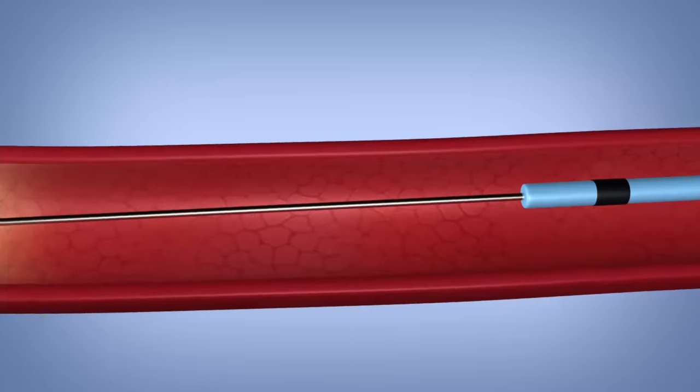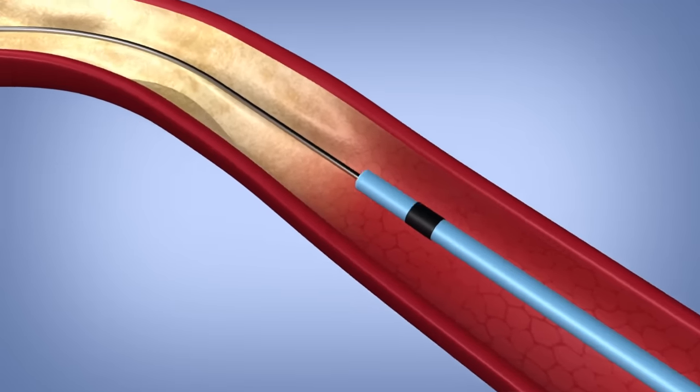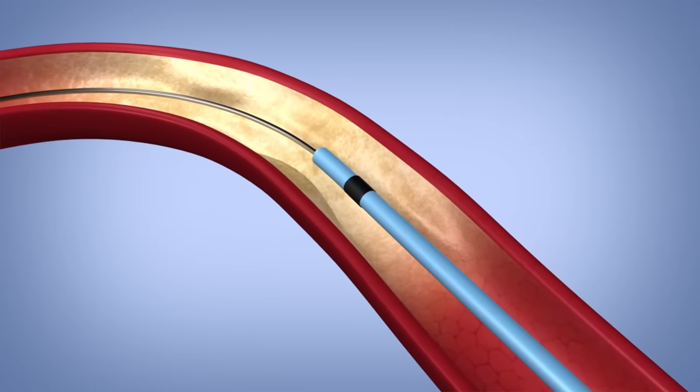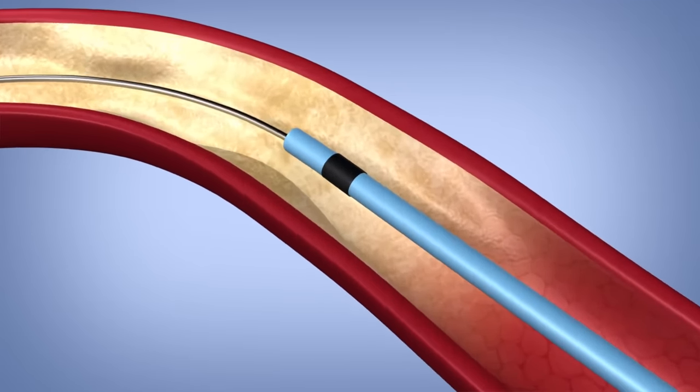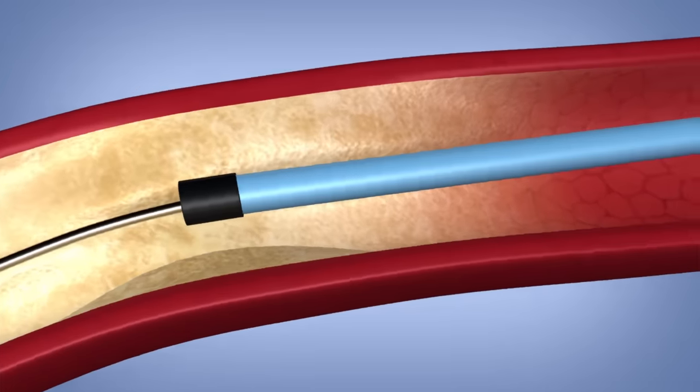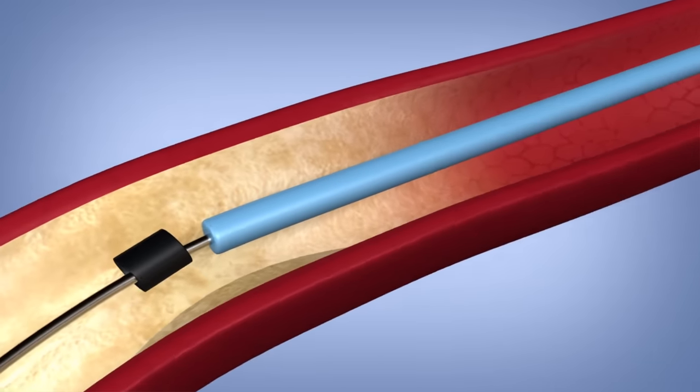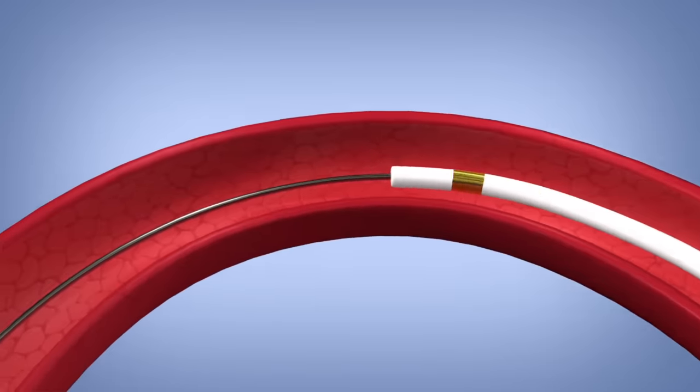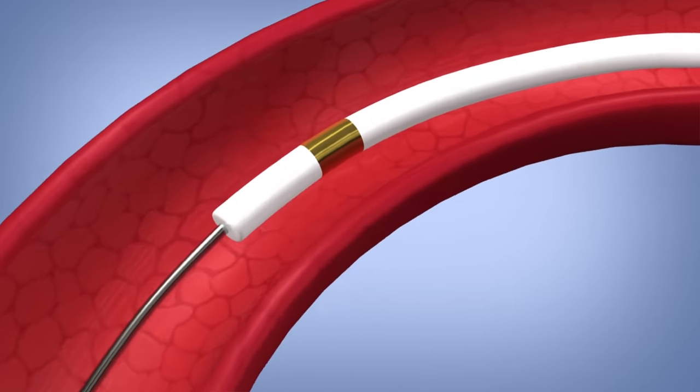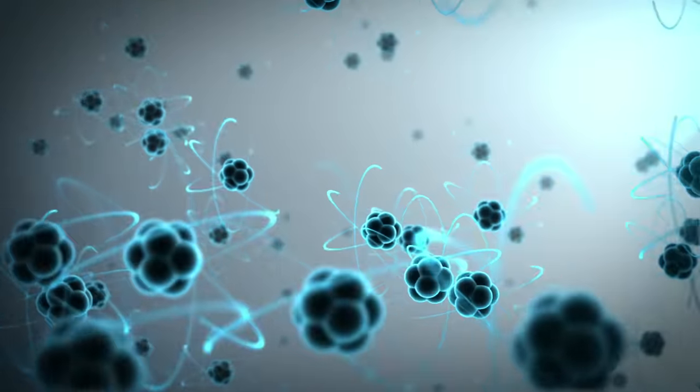Traditional radiopaque marker products have known risks: long-term storage degradation of metal-filled polymers and dislodgement of crimped-on marker bands. Through utilization of Visiband, these risks are eliminated because the radiopaque coating is bonded at an atomic level and does not degrade over time.